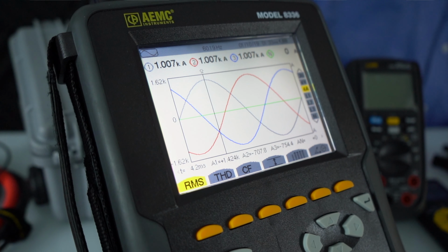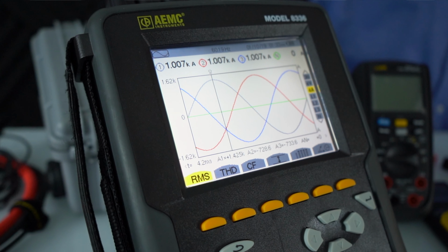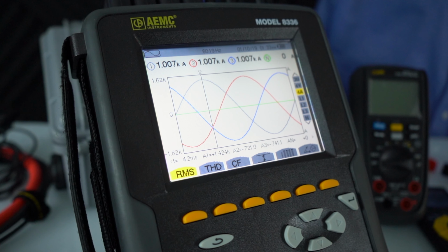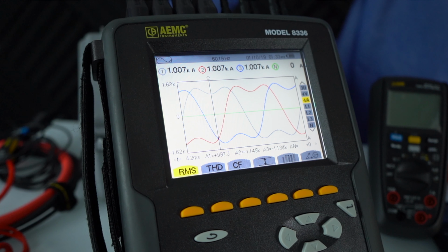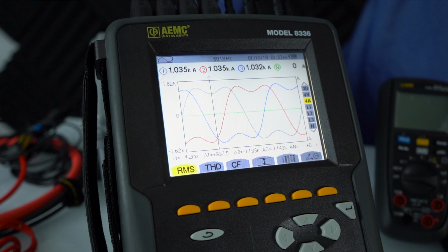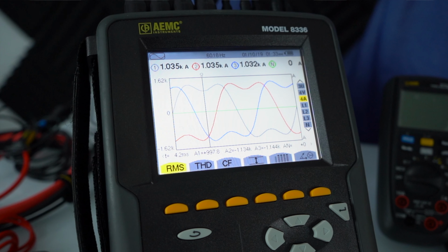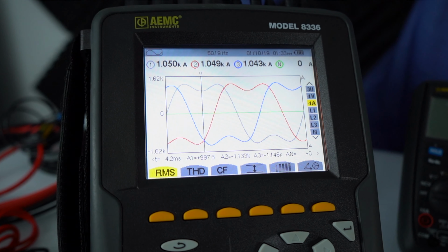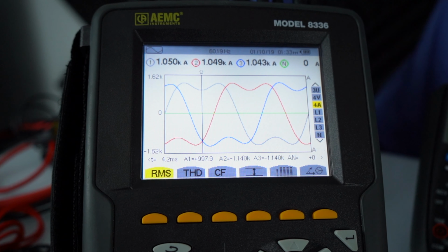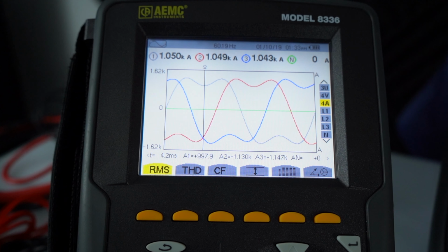The other thing that is really happening nowadays in the market is that harmonics are an issue too. What are harmonics? Those are opposing waveforms, other than your sinusoidal waveform, that distort the original sinusoidal waveform. Back in the day, we had motors that started across the line with a basic contactor, and those linear loads, as they were called, helped balance the nonlinear loads, like your switching power supplies.